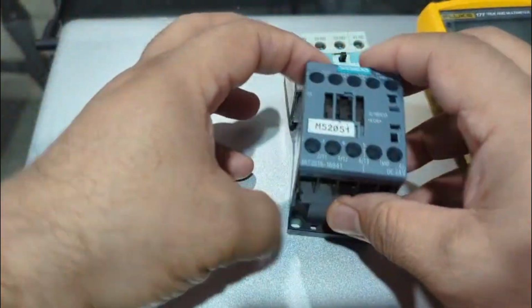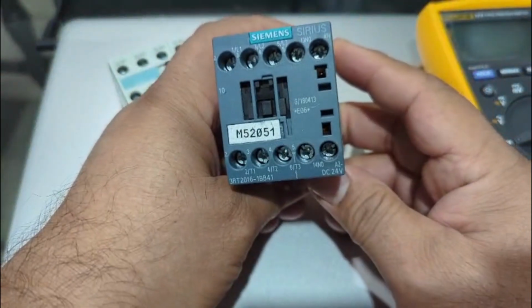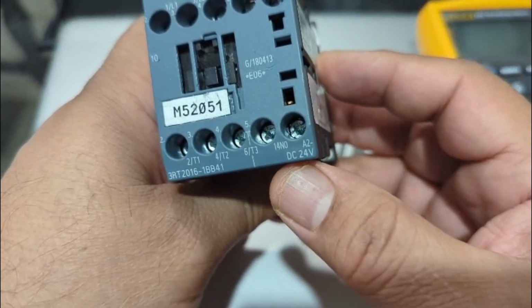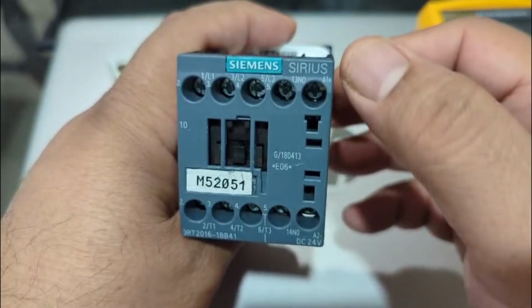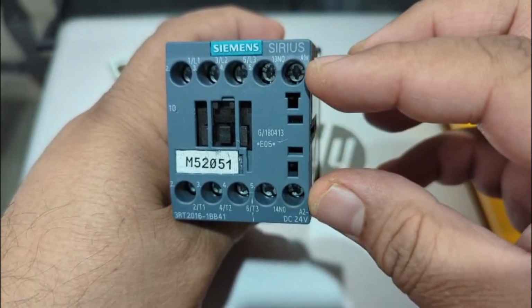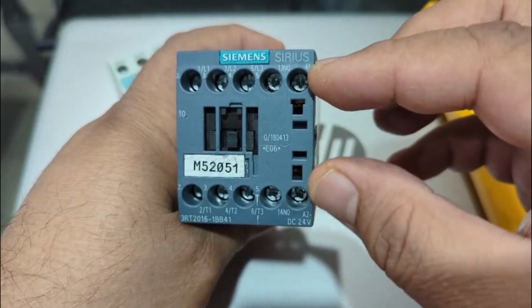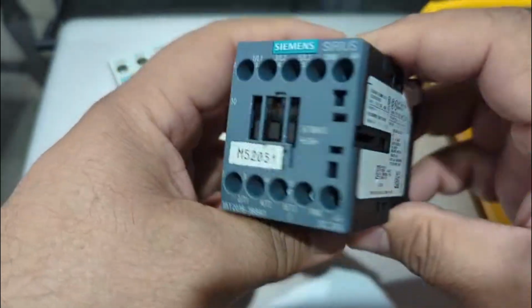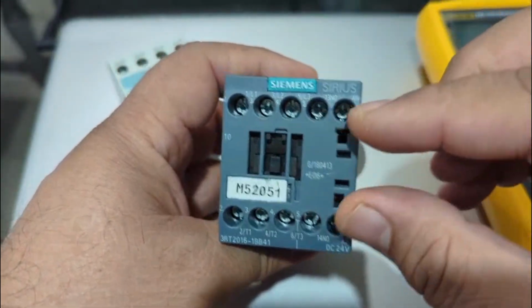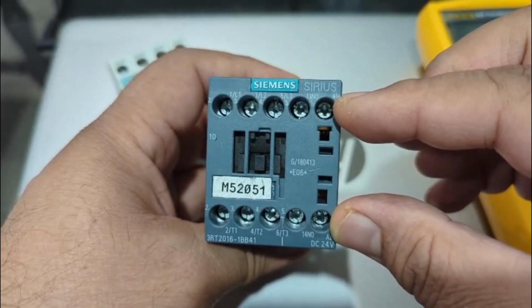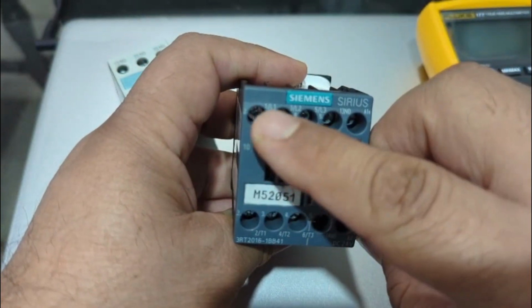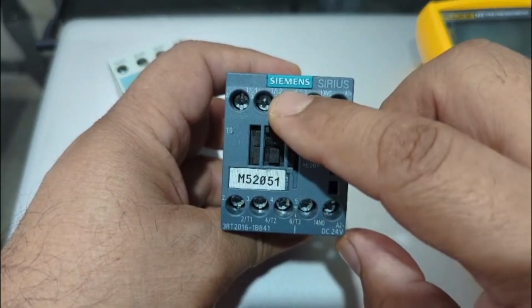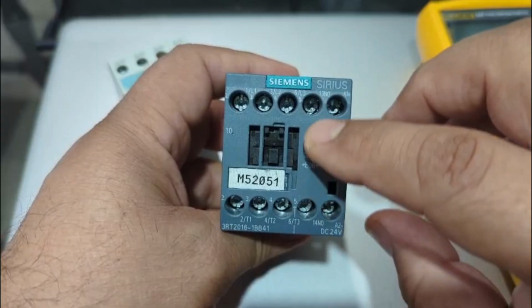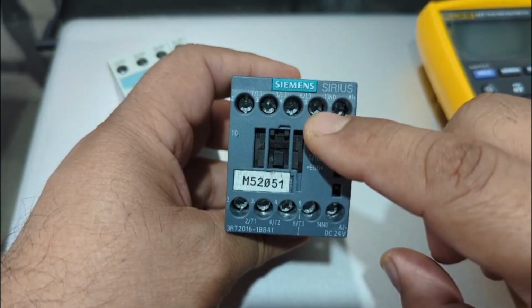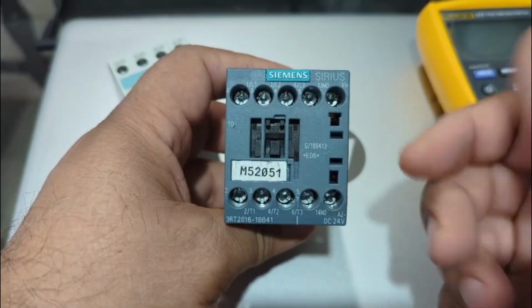Another thing, this is called a contactor, and I would like to explain. You see DC24, A2 and A1. These two terminals A1 and A2, where we have DC24, are called the coil or supply terminals. This is a coil terminal because it has a coil inside that energizes, so it's a magnetic contactor. These are supply terminals. Then we have different terminals like 1 2 3 4 5 6, and this one is the auxiliary contact. These all are open contacts. I will show you in the diagram.